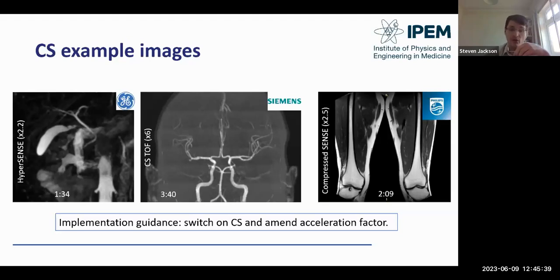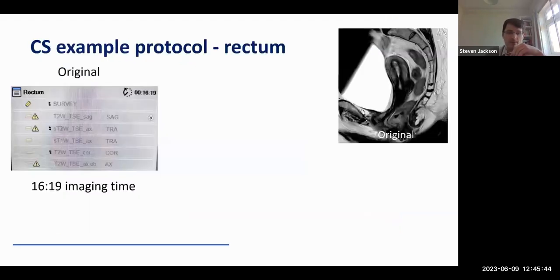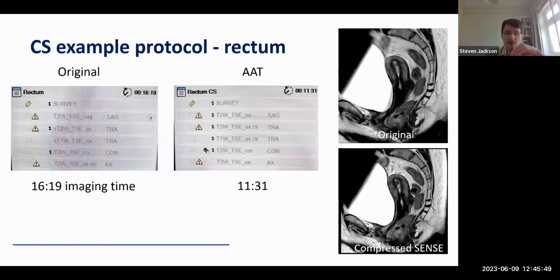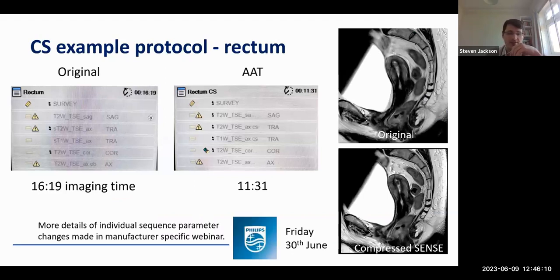An example protocol for rectum on a Philips 3T system: the original protocol was just over 16 minutes. After Compressed Sense was applied, the total sequence length within the protocol came down to 11 and a half minutes, with comparable image quality between the original and the Compressed Sense equivalent. More details of individual parameter changes will be in the Philips webinar on the 30th of June.